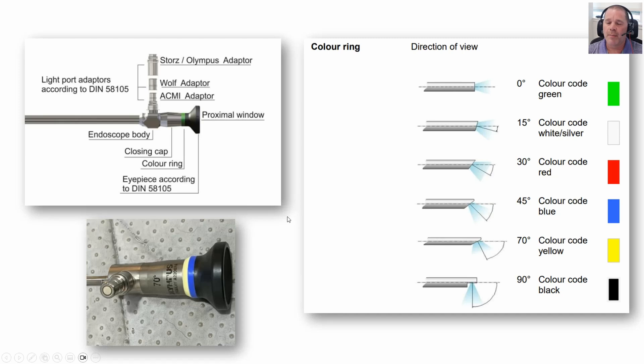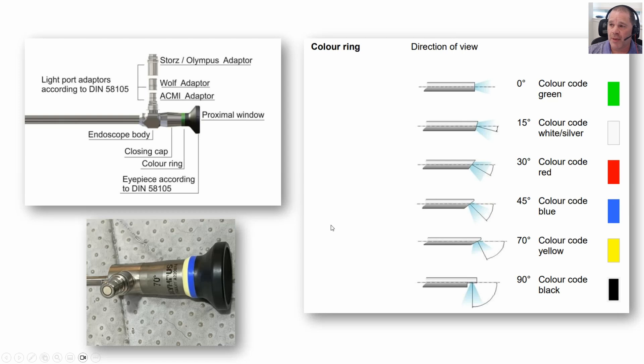When we talk about identifiers, there are some key identifiers used by different manufacturers. It's about: how do we high-level disinfect this, how do we sterilize it, what are we reprocessing it with, or what clinical accessories are required? This graphic here is showing a typical rigid endoscope — we can use different types of light post connections, light cable connections, illumination bundle connections — again those are universal terms that people use.